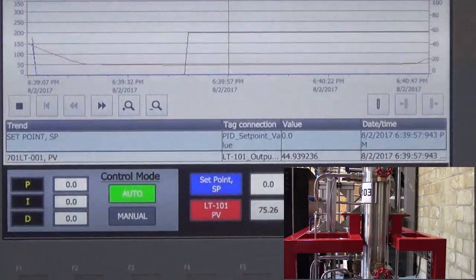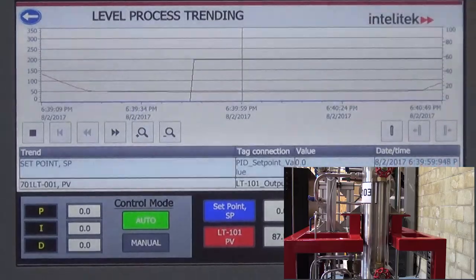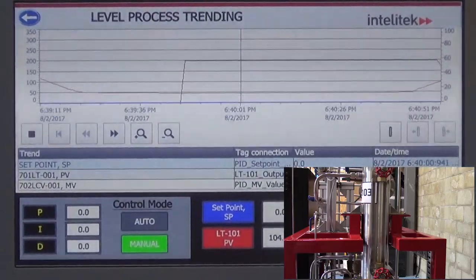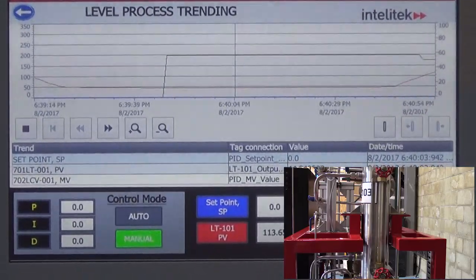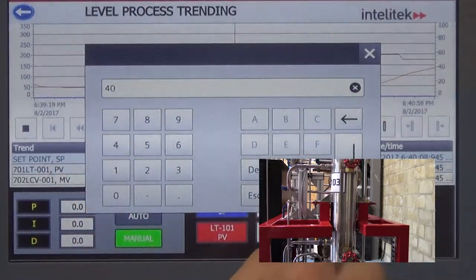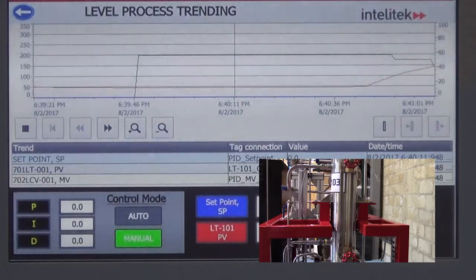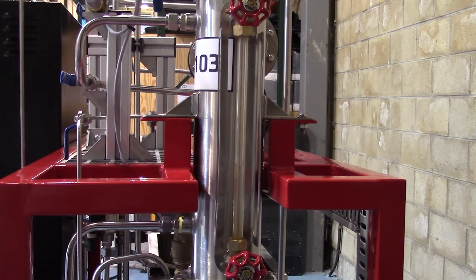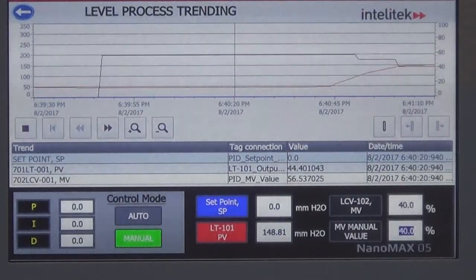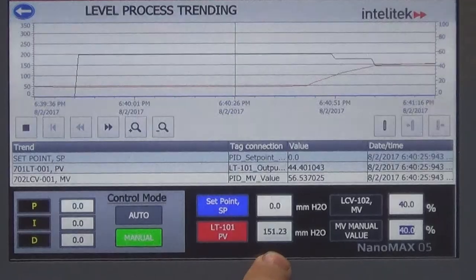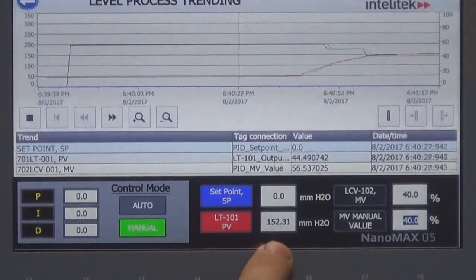And what we're going to do here is set, first, a manual value. So if we want our valve to control the liquid level to be open a certain amount, I can just type that in and the controller will automatically open this valve right here to a certain percentage, and the amount of water will rise or fall based on that. And you can see right here, this is the pressure sensor value, and right now it's rising.